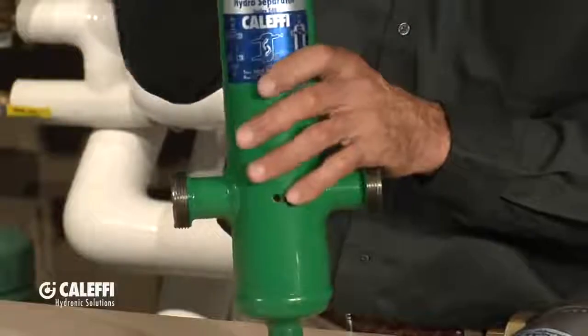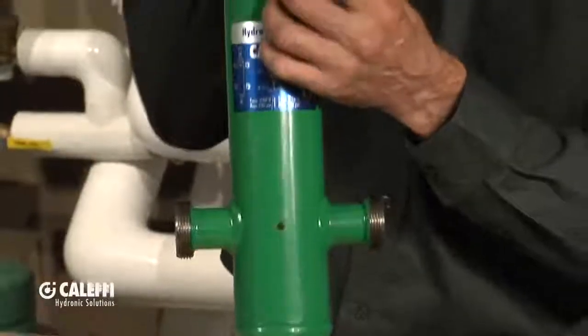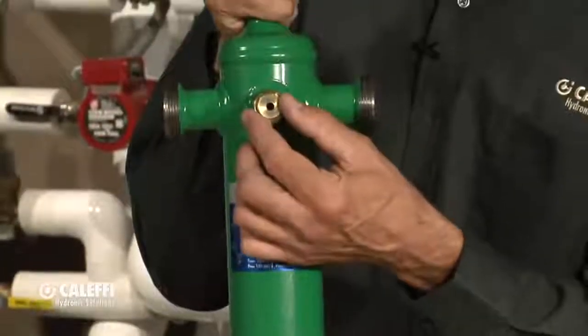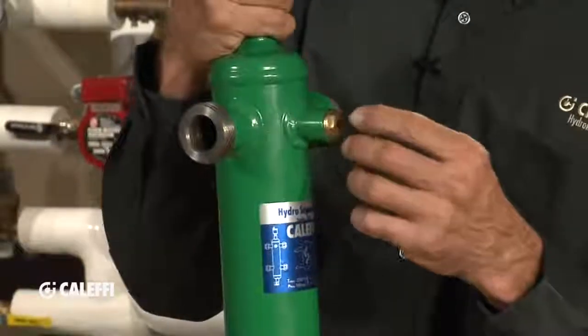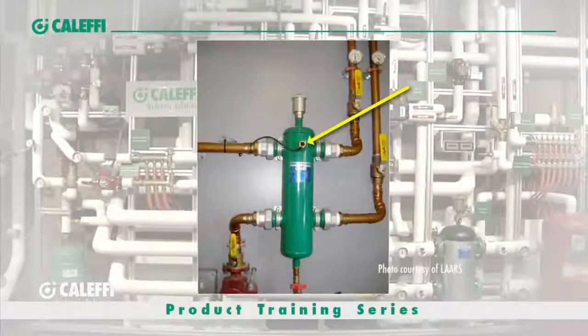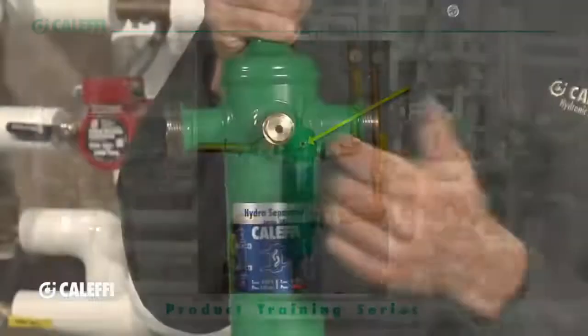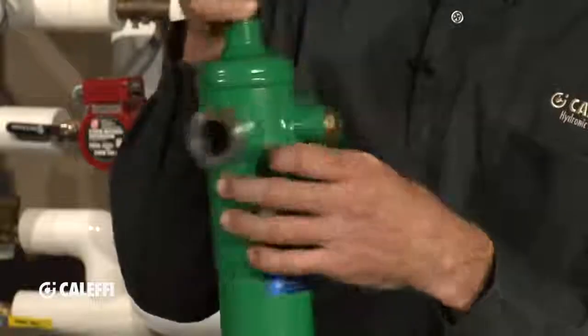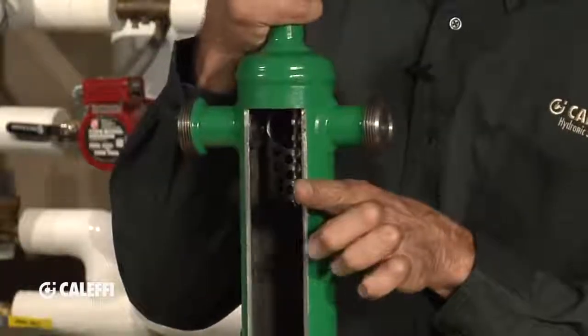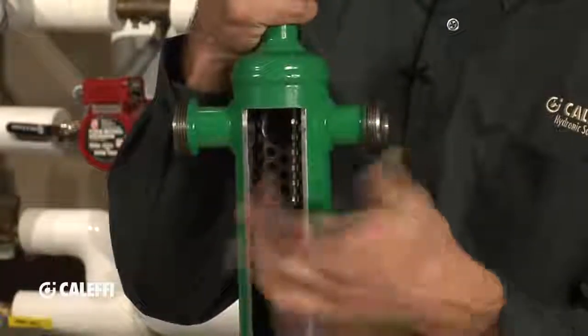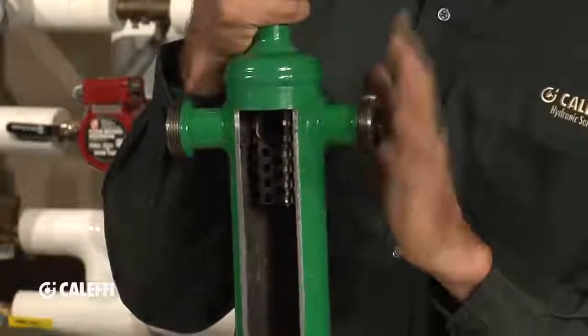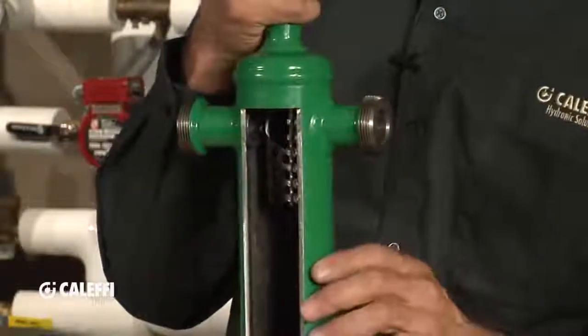One last thing that we give you on this is this port, and it's been drilled for a display unit, but that's a temperature port, so you can screw that out, and we've got a temperature well that screws into there. It's a dry well, and now you can stick a sensor in. A lot of installers like to trigger their boiler or their chiller from a sensor that's going right into that water, because that's a good sampling point for what's going on in your system. It's central to the separator, so it's going to read accurately what the flow temperature is going through there.